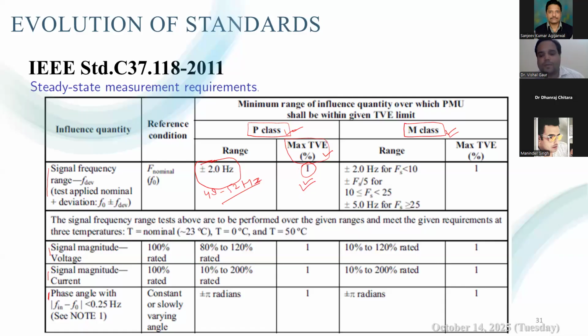Similarly, they have defined it for the M class. The M class PMU is intended for monitoring and detailed analysis purposes in the system. In that case also, they have defined the maximum total vector error as 1%, but corresponding to the reporting rate, meaning how fast your PMU is reporting the data. If the data reporting rate is 10 frames per second, then for plus minus 2 hertz frequency deviation, it must estimate the phasor with a maximum of 1% total vector error.